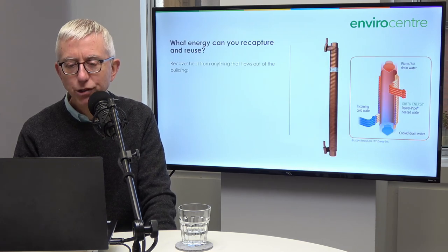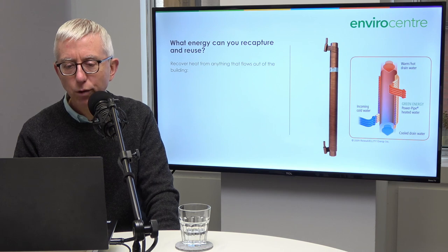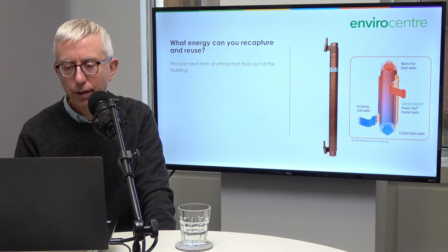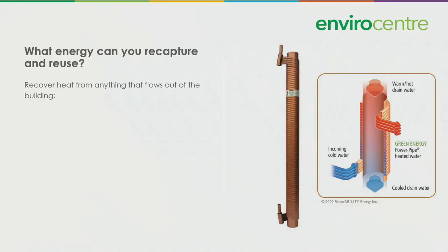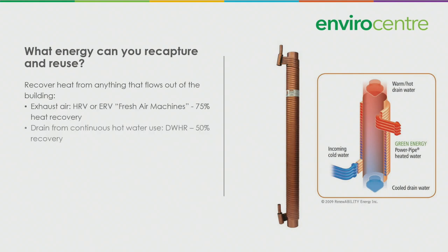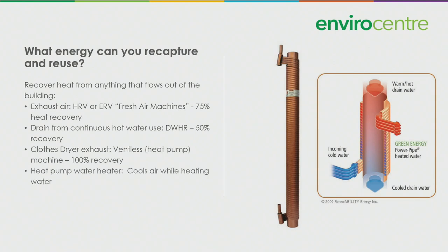What energy can you recapture and reuse? You can recover heat from anything that flows out of the building. And in this case, that's the drain water heat recovery unit. You can use, obviously, the HRVs or ERVs that we've already discussed, and the drain water heat recovery. If you have clothes dryers, you can also capture energy from the clothes dryer exhaust. Now we have heat pump clothes dryers that will recover all the heat from your exhaust. You don't have to vent them outside, so you can use clothes dryers to heat your house. You also have the heat pump water heater. Those are packaged systems that have the energy recapture built into them.